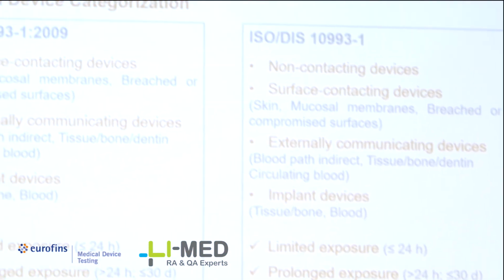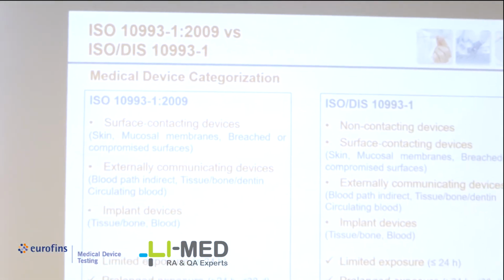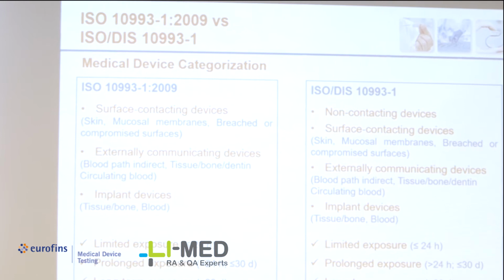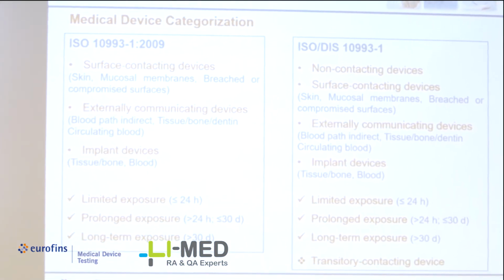We have also the externally communicating device that basically are placed totally or partially outside of the body, but have a contact with the inner part of the human body. And then we have the implant device. So, according to the categorization by nature of contact, now the committee draft includes a new category called non-contacting device. In this category, there are all the devices for which the biocompatibility assessment is not necessary, like, for example, a diagnostic software, because there is no direct or indirect contact with the human body, so the biological evaluation shouldn't be demonstrated.